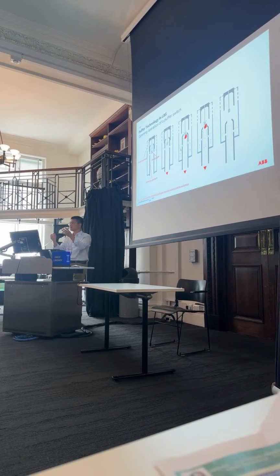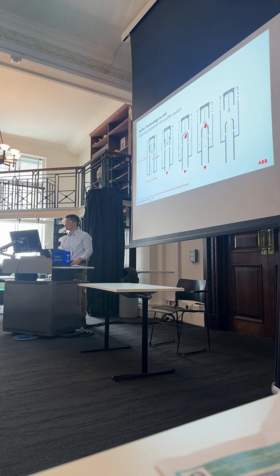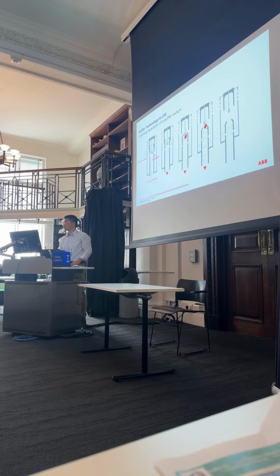By doing this, you blow the air to the arc point — you see the arrows of the airflow here. So during the opening process, you compress the air and it blows the arc directly, eliminating it. I'm not sure whether it is complicated, but the main idea is to really use the high pneumatic force to blow the arc.